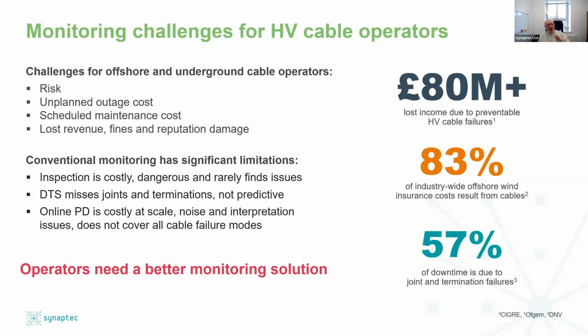The message here is that whatever kind of operator you are, I'm sure you recognize that there are challenges inherent with deploying cables. Not only are they much more expensive to install than overhead lines, but once they're down there, it's really hard to see things going wrong, and it could be dangerous to conduct regular manual inspections and visits to ensure they're okay. Scheduled maintenance costs are high, and in some cases, we've seen some truly shocking numbers involved in the cost of cable failures. The most extreme event you can see here that was actually published in the UK that came from an offshore wind failure was an outage cost that went to 80 million pounds or $100 million. That's an extreme case, but it happens.